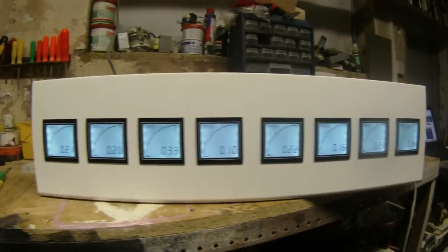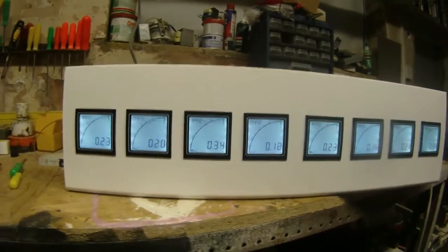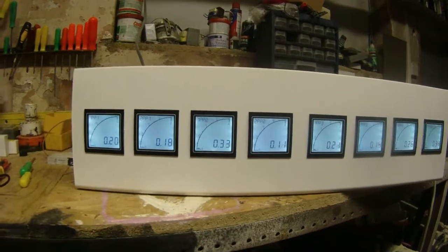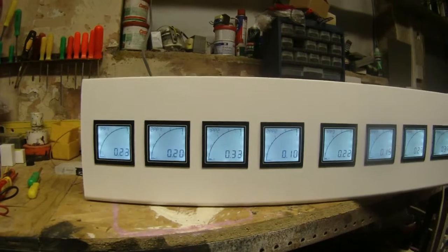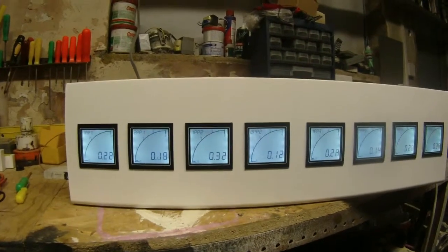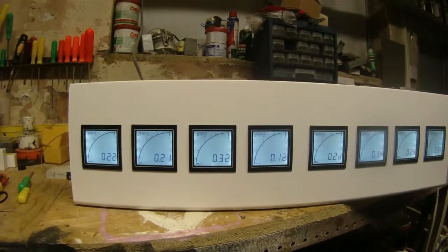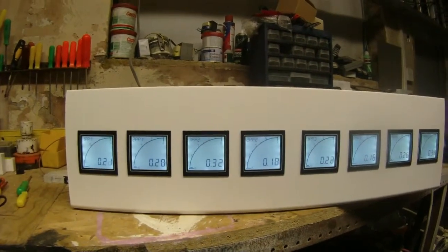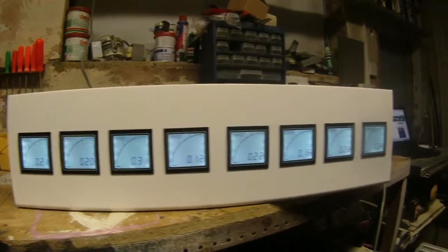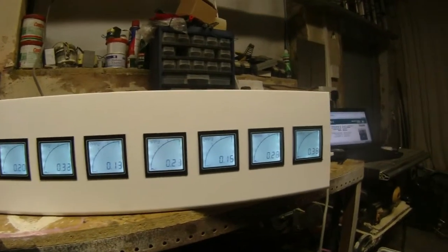The one tricky issue was setting up the CT ratios. According to the instructions, it made out you could set up virtually any ratio. One particular make did have a few issues with not registering anything at all when a test current was put on the system.